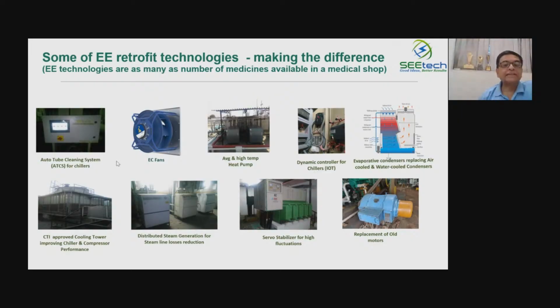EC fans is a very upcoming project. We are coming up with EC fans, wherein the savings are of the order of 30 to 50%. Here, energy efficiency exists in both forms: one is the motor efficiency we saw in the earlier case, and also the fans. Otherwise, if you see AHU fans, you will see them in the centrifugal format; this is basically the axial fan.